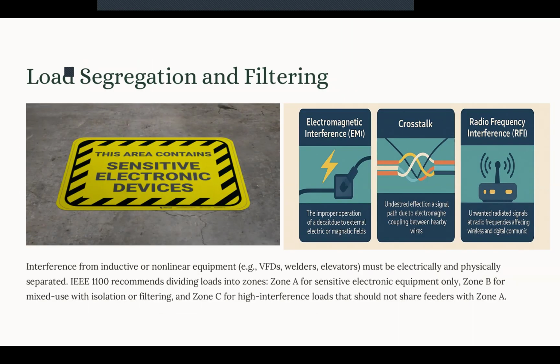Now, we mentioned load segregation and filtering several times. This is because we want to isolate sensitive electronic equipment from the electrical noise, transients, and harmonics that are generated by other types of loads. Electrical disturbances can propagate through shared feeders and can cause data corruption, logic errors, or resets in those sensitive equipment. And if we have proper load segregation, it prevents cross-coupling of those disturbances by using dedicated feeders and physical separation.